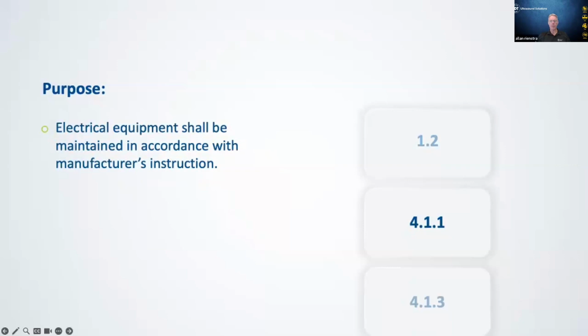4.1.1, it's straightforward, but it's critical. It establishes that electrical equipment must be maintained according to the manufacturer's instructions. The reasoning is pretty simple and common sense to me. The manufacturer knows the design, knows the tolerances, and knows the safe operating limits of their equipment. So by following their guidance, organizations are not only complying with NFPA 70B, but they also protect both the safety of personnel and the reliability of the asset.